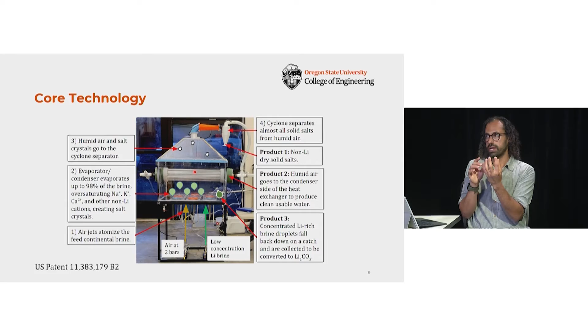Number three is when you have dry spots. That's really the answer to the question: if you have a spray that evaporates on a surface, over time, regardless of what you do, you'll get salts building up. The good thing is the same spray carries fresh water that can wash it away. But in a steady-state, non-moving system, you keep doing the same thing on the same spots—some spots are perpetually wet, some perpetually dry, and buildup occurs.